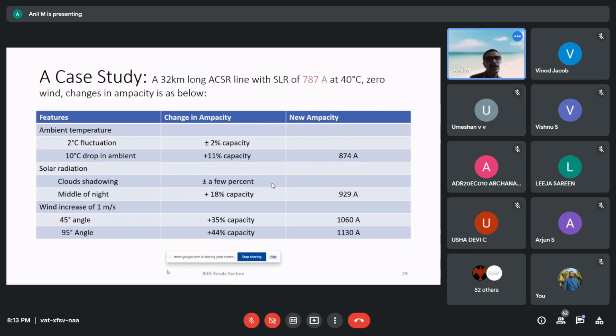Then in the presence of wind, when wind speed increases by 1 meter per second, if the wind is blowing at a 45-degree angle to the conductor lay, then plus 35% capacity is achieved, 1060 ampere instead of the SLR rating of 787 ampere. And if the wind is blowing at a 95-degree angle, plus 44% ampacity enhancement is obtained. That is, instead of the SLR of 787 ampere, we will get 1130 ampere.